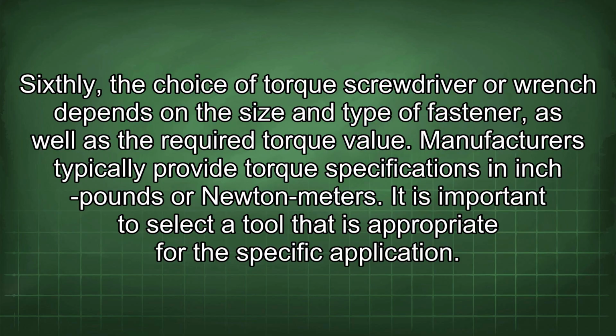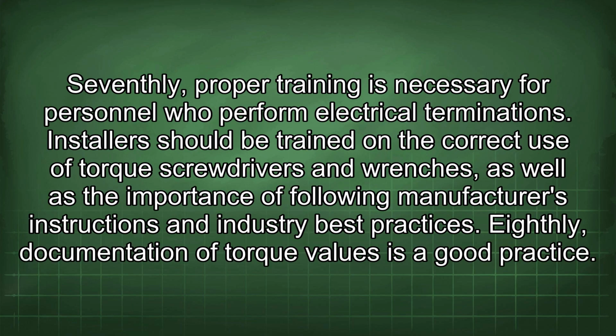Sixthly, the choice of torque screwdriver or wrench depends on the size and type of fastener, as well as the required torque value. Manufacturers typically provide torque specifications in inch-pounds or Newton-meters. It is important to select a tool that is appropriate for the specific application. Seventhly, proper training is necessary for personnel who perform electrical terminations. Installers should be trained on the correct use of torque screwdrivers and wrenches, as well as the importance of following manufacturers' instructions and industry best practices.